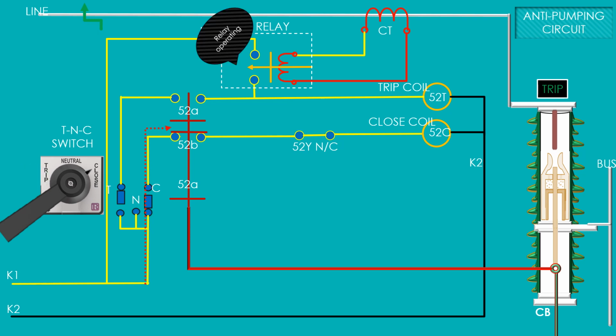If the circuit breaker is given a closing pulse and the holding time of the pulse is too long, then firstly the circuit breaker will be closed and thereafter will be tripped due to operation of the protection relay, which will be energized by the faulty current of the line through the line CT.